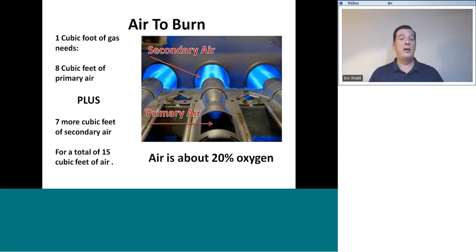8 cubic feet of primary air contains enough oxygen to sustain combustion. But in an actual gas burning appliance, 8 cubic feet of air is not enough. Primary air, as we just discussed, the 8 cubic feet of primary air enters the burner along with the gas right at about the same place. As the natural gas is being delivered under pressure, and it's a very low pressure, it bridges this gap on its way down the burner tube, causing air to be drawn in and mixed with the gas.